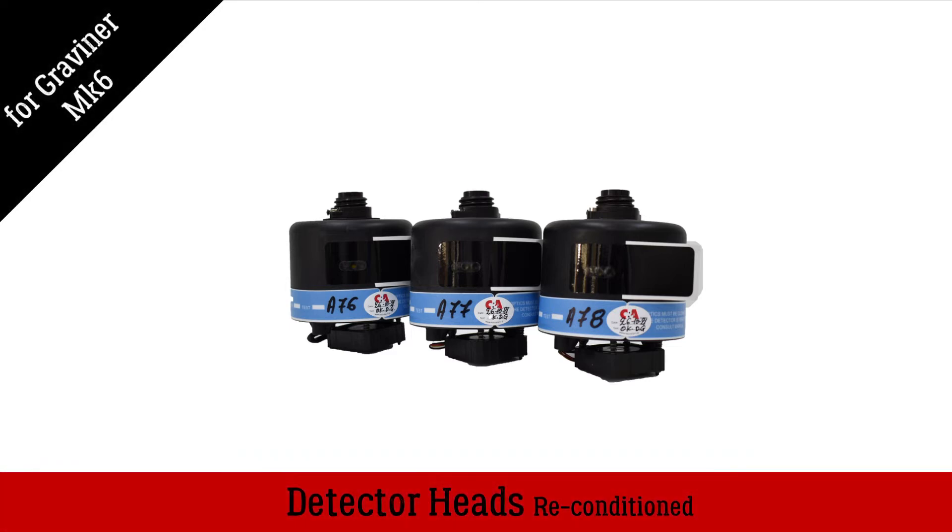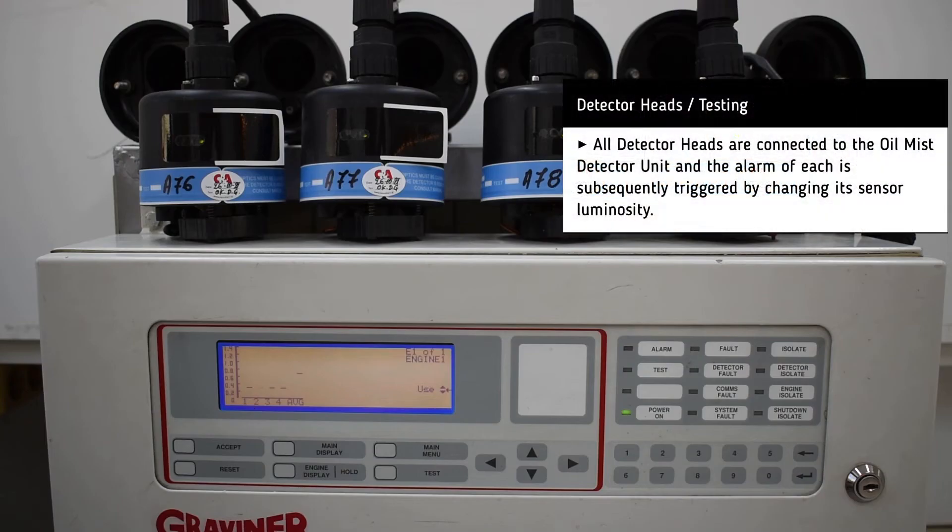Recondition detector heads for Graviner Mk6 oil mist detector. For testing, the heads are connected to a spare oil mist detector unit, and we simulate the oil mist with smoke detector testing gas sprayed on the head's path.